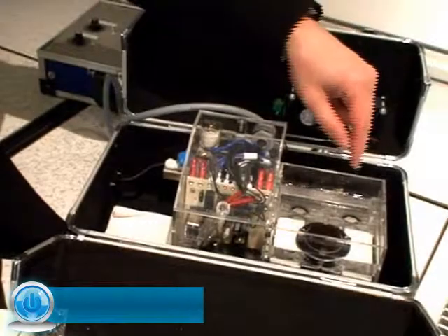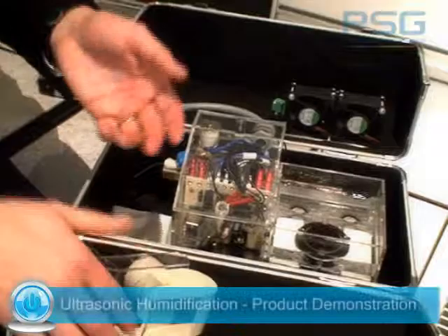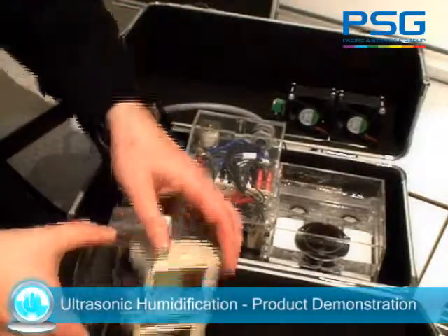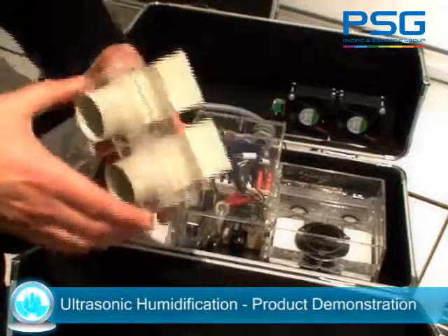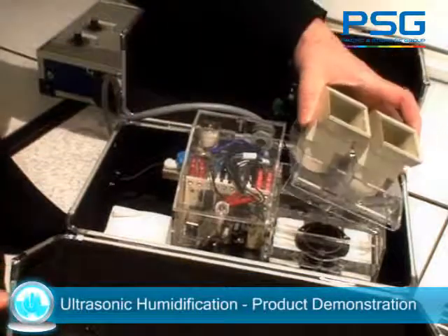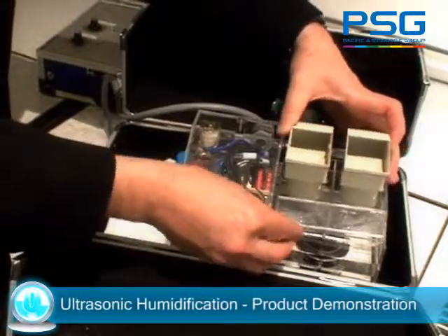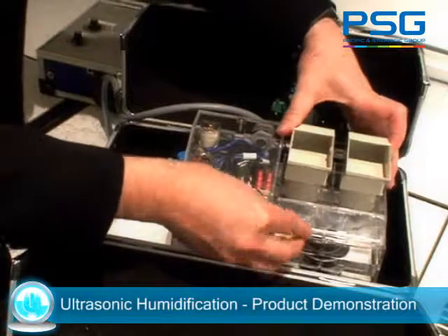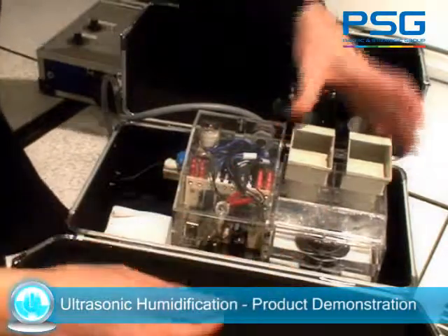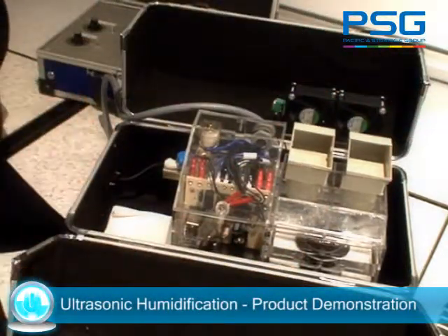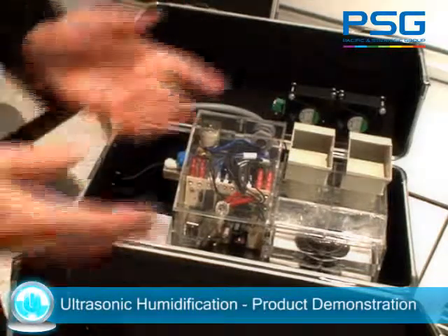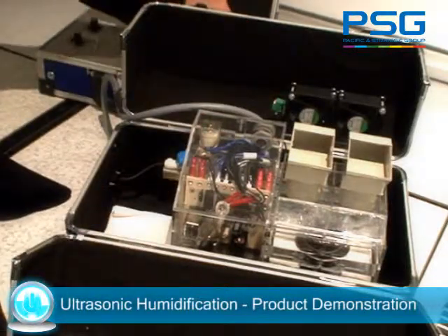So the way it works is two transducers vibrate at very high speed. They create a column of water inside these chimneys. At the edge of that column of water, very fine water droplets are produced. As I said, this is a mechanical process, so we're not heating up the water like an immersed electrode humidifier. It's actually a mechanical process without adding any heat.